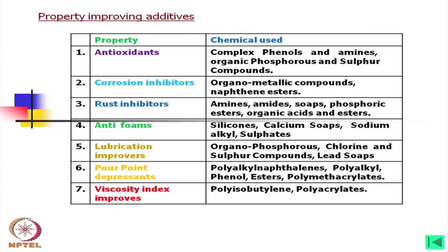The first additive property: antioxidant — for that, complex phenols and amines, organic phosphorus and sulfur compounds are used. Corrosion inhibitors — organic metallic compounds and naphthenic esters are used. Rust inhibitors — amines, soaps, phosphoric esters, organic acids and esters.